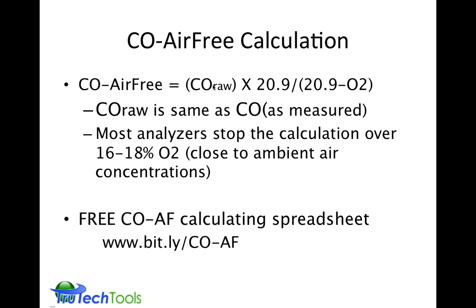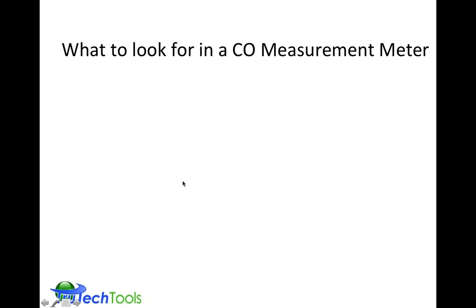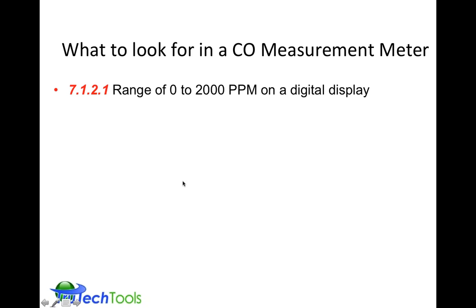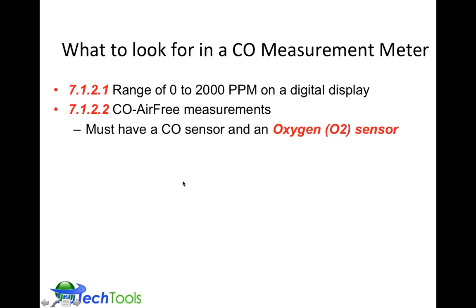There's actually a spreadsheet I developed. You can go to this short link, bit.ly/CO-AF, uppercase CO dash uppercase AF for CO air-free. And you can play around with it and enter some values in, and it would do the calculation for you if you did not have a combustion analyzer that does the CO air-free calculation, which I highly doubt because they've been doing that for decades. So what do you look for in a CO measurement meter? Going back to the standard again, it's got to read up to 2000 ppm.